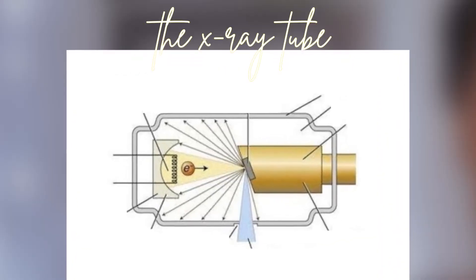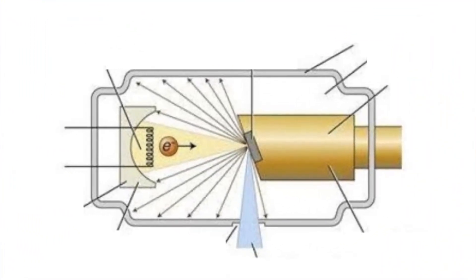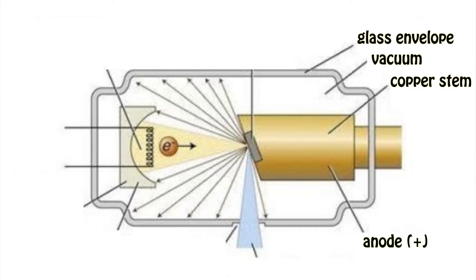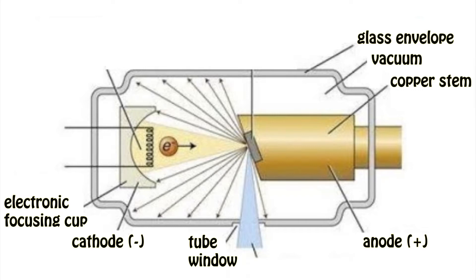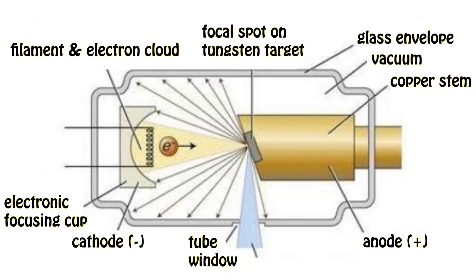Now let's take a look at the major components of the x-ray tube. We have the glass envelope that the tube is housed in, the vacuum, the copper stem, the anode, the tube window, the cathode, the electronic focusing cup, the filament and its electron cloud, the focal spot on a tungsten target, and when the x-ray is produced it escapes through the tube window and we get the useful x-ray beam.